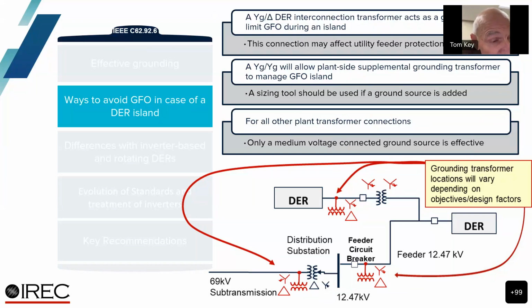The most common transformer used in the U.S. is the second one, the Y ground, and that allows the information of the fact that a fault's occurring, we call it a zero sequence, to be passed through the transformer. Now, for solar systems which basically run ungrounded, that doesn't really help. If the solar keeps generating and it being ungrounded, it won't see the fault and it'll cause that over voltage.